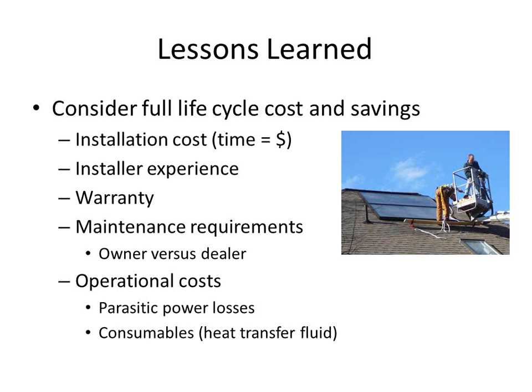When looking at life cycle costs, maintenance requirements are also key. Some systems require, for the warranty to be honored, that the heat exchanger fluid is changed every year or other year. The fluid is generally somewhat expensive, in the $30 to $40 per gallon range for the glycol. So the two factors you have to look at are how often the fluid needs to be replaced and how much fluid is in the system.